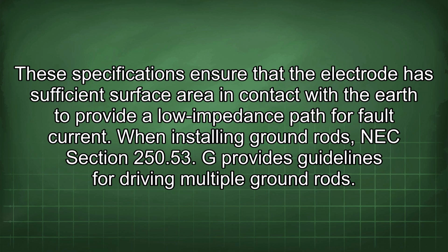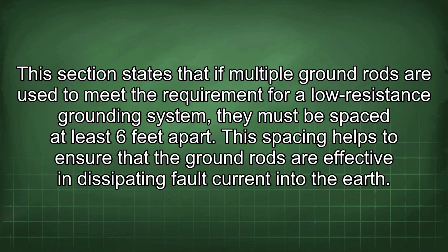When installing ground rods, NEC section 250.53(G) provides guidelines for driving multiple ground rods. This section states that if multiple ground rods are used to meet the requirement for a low resistance grounding system, they must be spaced at least 6 feet apart. This spacing helps to ensure that the ground rods are effective in dissipating fault current into the earth.